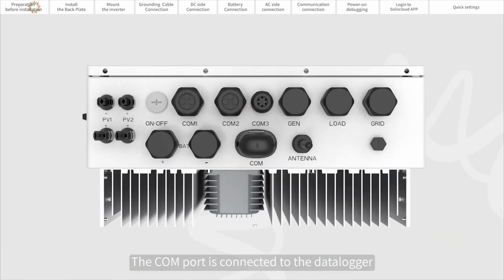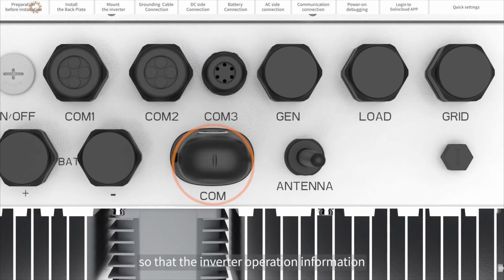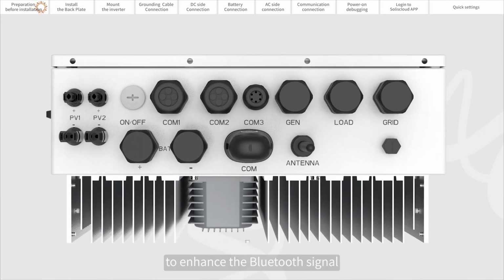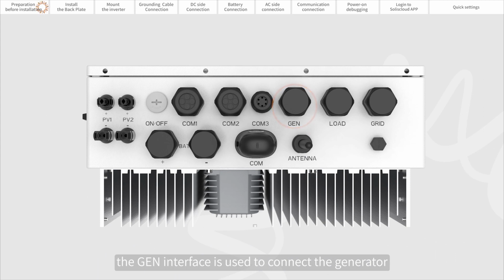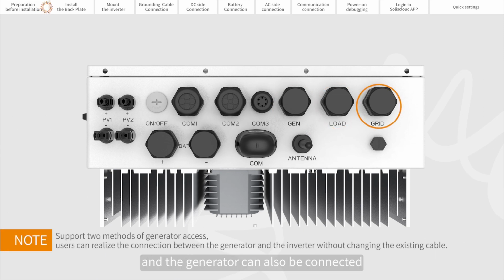The COM port is to connect the data logger so that the inverter operational information can be uploaded to the Solis Cloud platform. The antenna port is connected to the antenna to enhance the Bluetooth signal. The GEN interface is used to connect to the generator. The LOAD is used to connect to the backup load. The GRID is used to connect to the grid, and the generator can also be connected to the grid port through the automatic transfer switch.